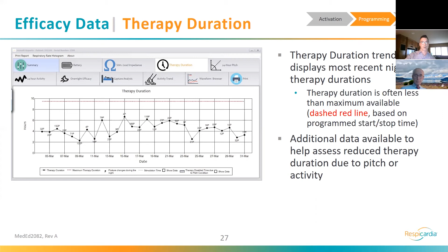In the legend, I have a couple toggle items that allow me to look at the actual times that are lost due to activity or rolls from say supine to a right or left position. And then also therapy duration lost due to this violation of our pitch threshold. Really clues us in on to perhaps there's a programming change that's a result or why therapy durations are low. Generally, I like to see at least 75% of the maximum duration or higher.